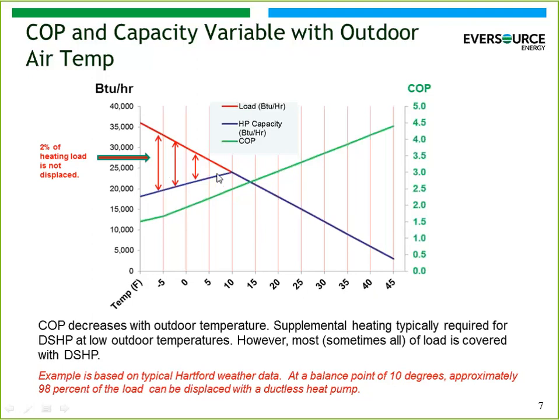Basically, what you see, this little triangle here, is the gap that's left between the heating load on the house and what the heat pump is able to provide. When you look at this graph, the first thing that might jump out in your mind is, wow, that's a pretty big triangle. Should I make my heat pump bigger in order to satisfy that load? Because that looks like a fairly big chunk, at least compared to the rest of the graph. And my answer is maybe.